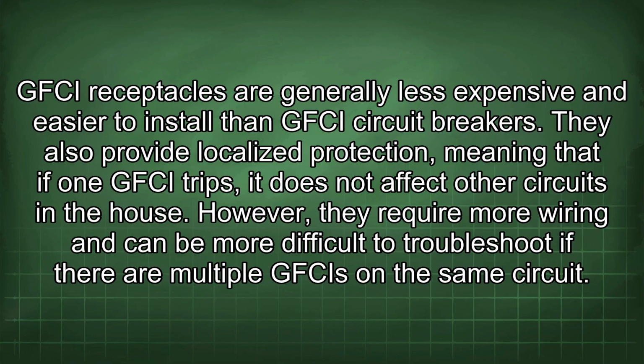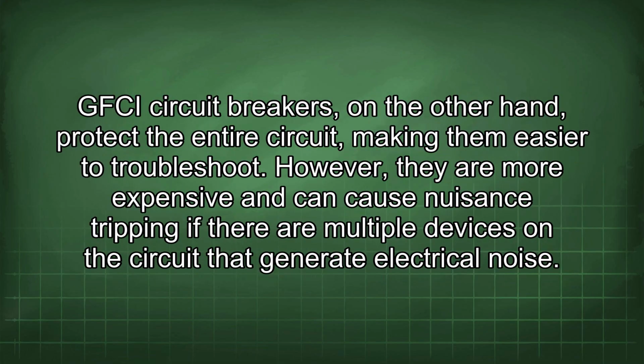GFCI receptacles are generally less expensive and easier to install than GFCI circuit breakers. They also provide localized protection, meaning that if one GFCI trips, it does not affect other circuits in the house. However, they require more wiring and can be more difficult to troubleshoot if there are multiple GFCIs in the same circuit. GFCI circuit breakers, on the other hand, protect the entire circuit, making them easier to troubleshoot.